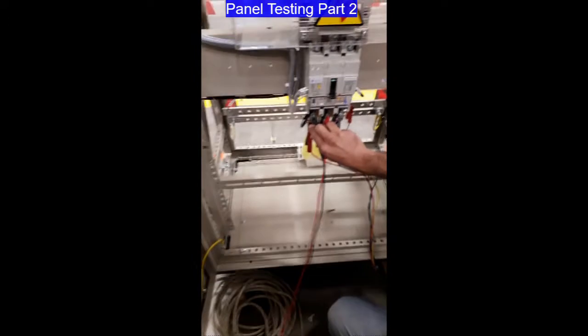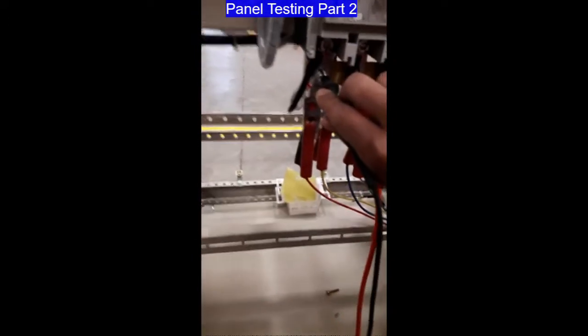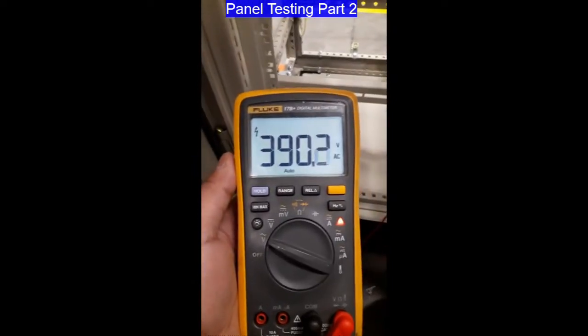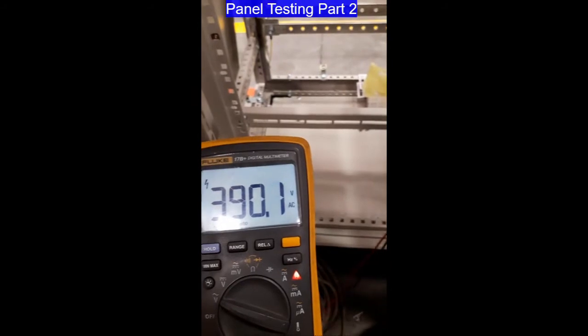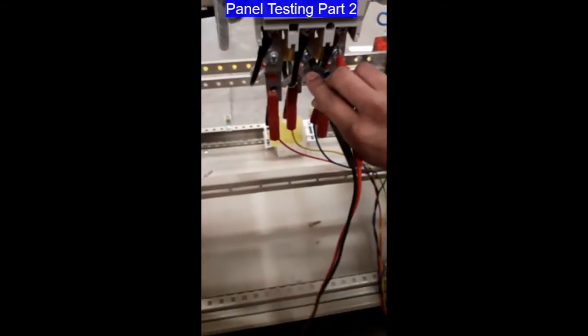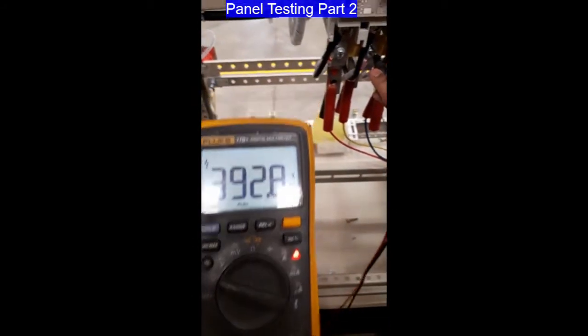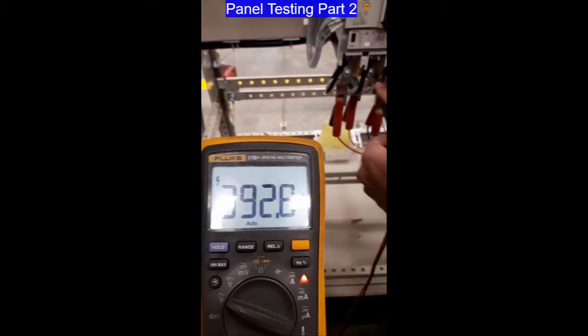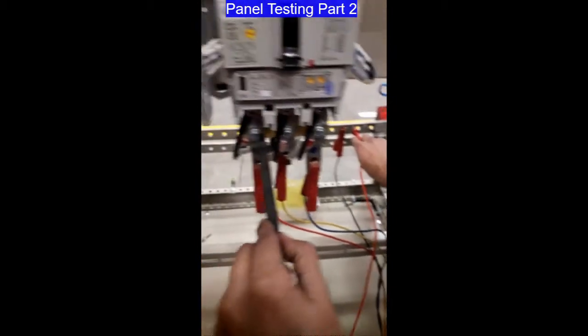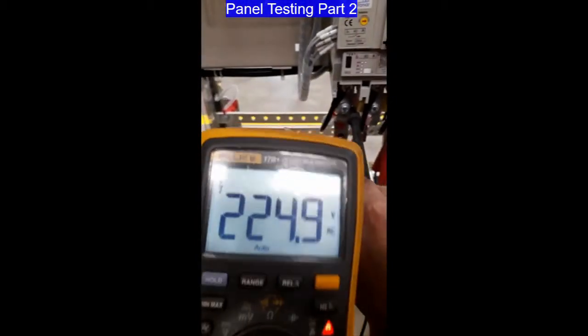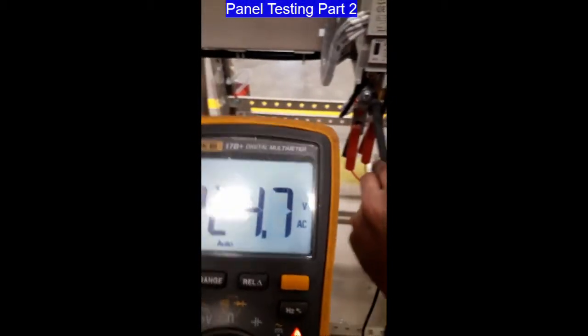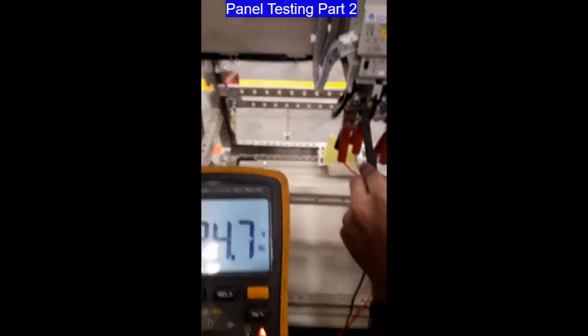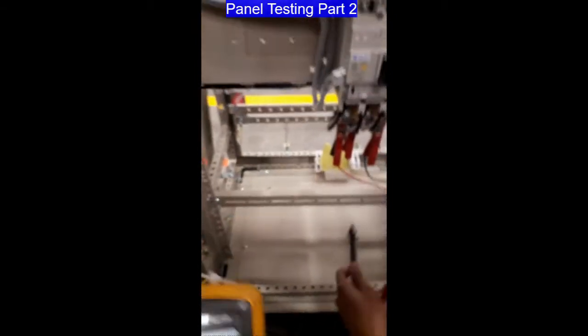Right, so now we are going to proceed to the functional test. Here our incoming supply is available. Line to line, this is the supply. Then line 2 to line 3, please. Okay, line 2 to line 3. Can you please give me phase to neutral? Okay, phase to neutral, this is the result, 220. Alright, so we will proceed now. Switch on the breaker, please.